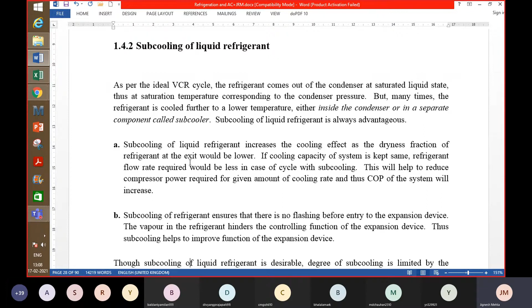The reason is that, as was shown from the chart, instead of point 3, if you subcool it, that line, assuming the pressure remains constant, runs very close to the saturated liquid line, and it will come out at 3 dash. And this is delta T subcooling. After that, if you expand it, you see that the dryness fraction at 4 dash is lower than the dryness fraction at 4. Because of that, in the same cycle, you get an additional cooling effect. And because of that, the COP of the cycle will be higher, because ideally the compressor work is not affected and your cooling effect has increased. So obviously the COP will increase.